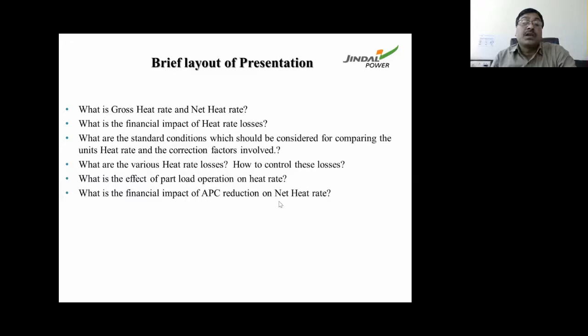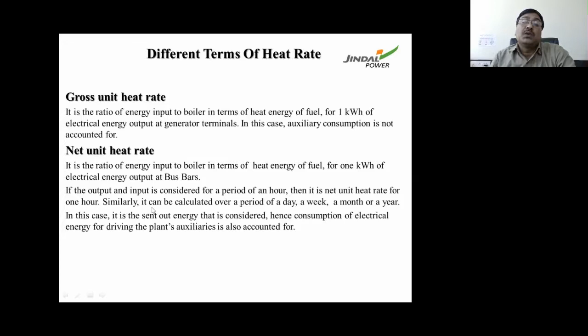First of all, what is gross unit heat rate? As we all know, it is the ratio of input energy to the boiler in the form of coal, heat energy, or fuel, per unit of electrical energy at the generator terminals. The net unit heat rate is the same as the gross unit heat rate, except that here we consider the output at the export terminal, so auxiliary power consumption is also included. If the output and input are considered for a period of an hour, then it is the net unit heat rate for 1 hour. Similarly, it can be calculated over a day, a week, a month or a year.